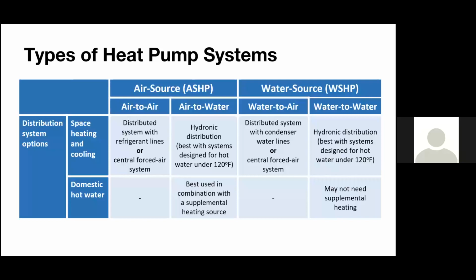But again, there are good reasons to use a hydronic-based system, air to water. One of them is on the domestic hot water side. There's more and more technology becoming available to heat or cool, including domestic hot water with an air source machine. So they actually do exist residentially for hot water heaters. They exist commercially as well. There's a big challenge there because you're not just trying to heat air inside a building and keep it around 70 degrees. You're trying to make hot water at 140 degrees. So think about that temperature range between the 140 degree water and the 0 degree outdoor ambient. So that's where some of those challenges come in. But again, the technologies are definitely catching up.